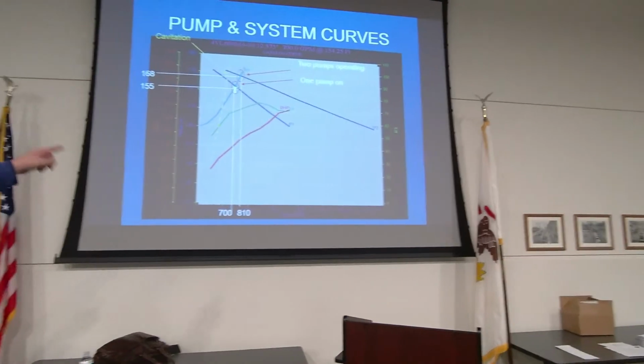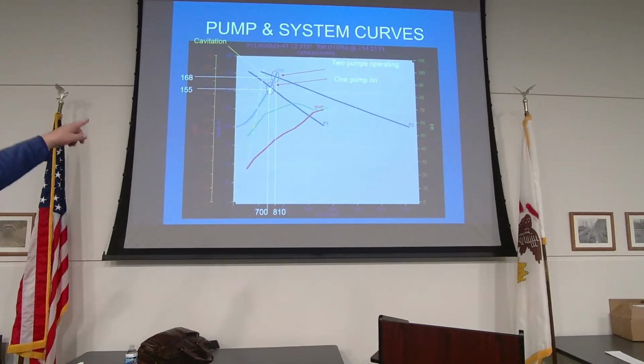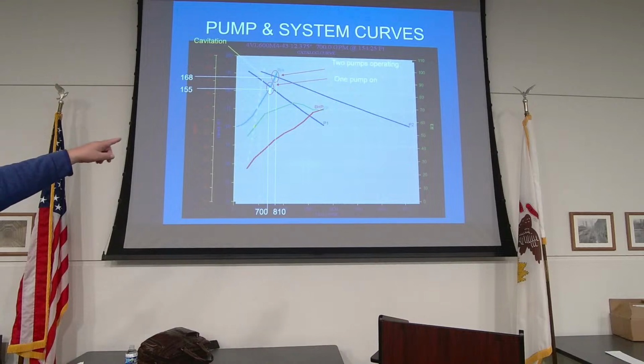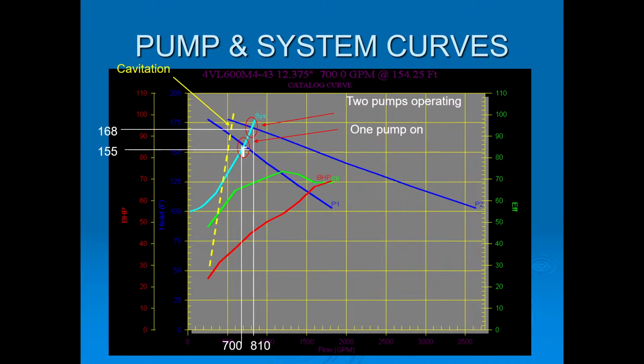As we go up, this is that station right there. One pump is the blue line, P1; P2 is pump 1 and pump 2. But you can see that friction goes way up. When it goes way up, that centrifugal impeller can only do so much, and in this case, it starts to cavitate off to the left.